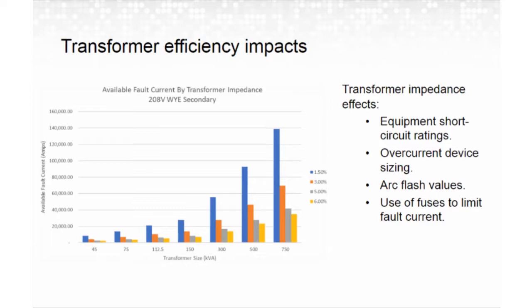One way to reduce load losses is to reduce winding resistance. A common transformer impedance rating around 5% has been used for decades. In an effort to reduce load losses, however, lower transformer impedance ratings have been offered more recently. So this graphic depicts the available fault current in several transformer sizes and four different impedances. Transformer size increases from left to right, from 45 kVA to 750 kVA. The blue bar there depicts a 1.5% impedance. Orange illustrates 3%, gray is 5%, and yellow is 6%.